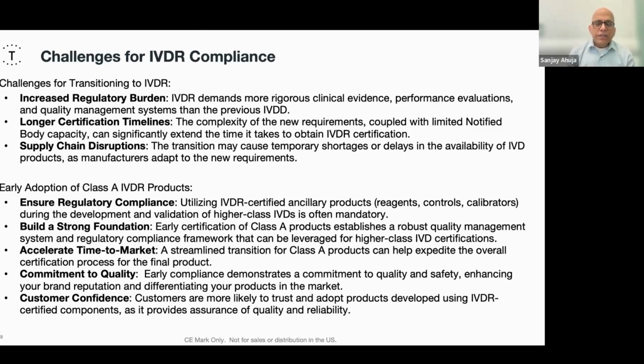Really, utilizing IVDR certified ancillary products like your reagents, controls, and also calibrators during the development and validation of higher class IVDs is often mandatory, because if your suppliers become critical because they are providing you with these controls, the suppliers are required to be open to unannounced audits. But if you have a Class A IVDR product, or a supplier who is under ISO certification already, the notified body is going to think, yes, the supplier has an ISO certification, and so the tendency of unannounced audits is minimized for the supplier. So obviously there's a benefit to the supplier, but also a benefit to the customers, the clients who are developing and validating the higher classification IVD products.